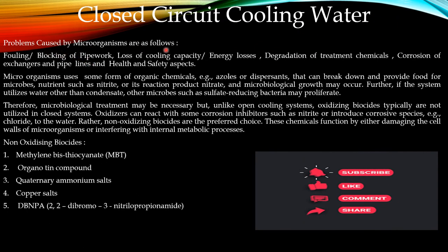Problems caused by microorganisms include fouling and blocking of pipes, power loss, loss of cooling water capacity, energy losses, degradation of treatment chemicals, corrosion of exchangers and pipelines, and health and safety impacts. Microorganisms can use organic chemicals such as azoles or dispersants as food. Nutrients such as nitrite and its reaction products can promote microbiological growth. If the system utilizes water other than condensate, microbes such as sulfate-reducing bacteria (SRB) may proliferate, further increasing microbiological growth.